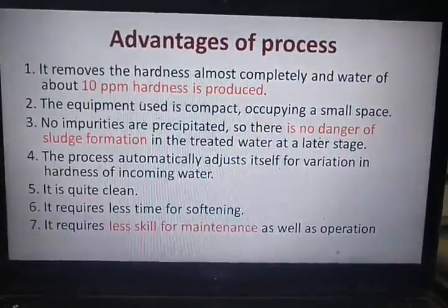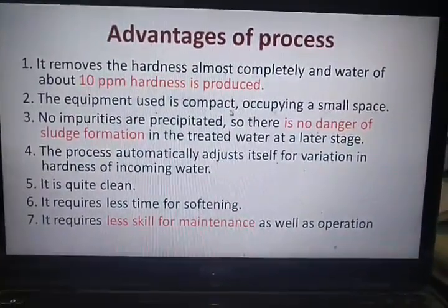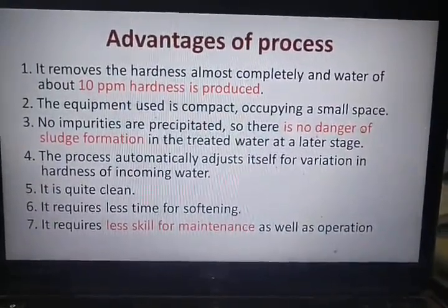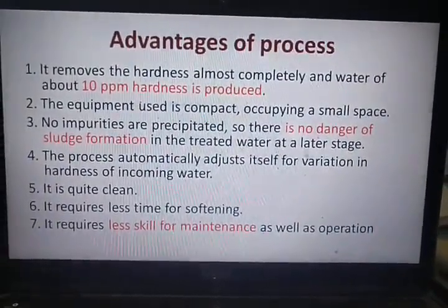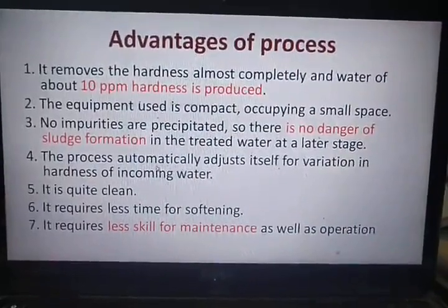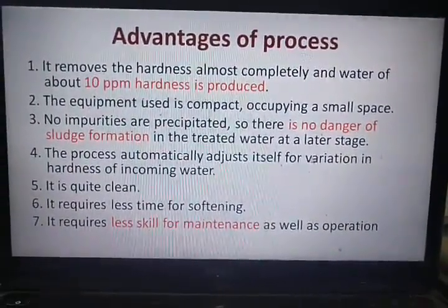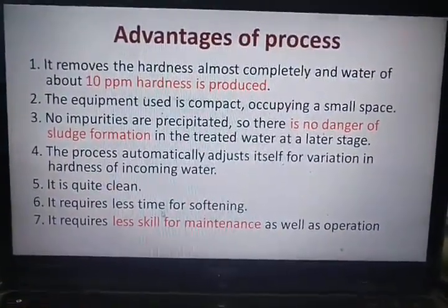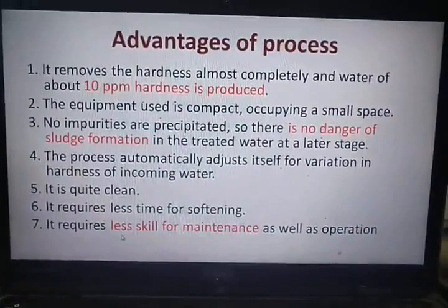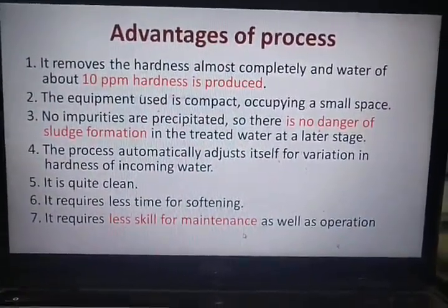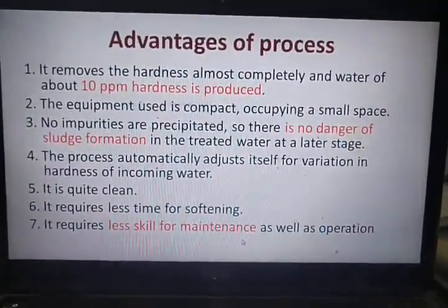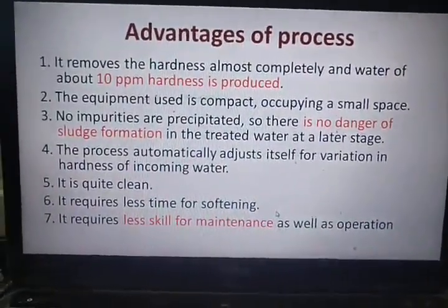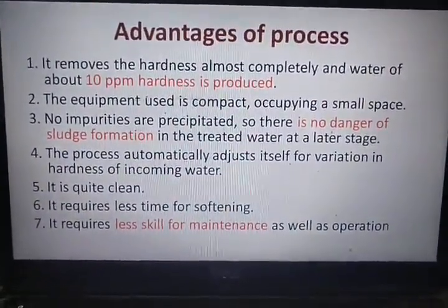The equipment used is compact and it occupies very small space. Here no impurities are precipitated, so there is no danger of sludge formation in treating water at a later stage. The process automatically adjusts itself for variation in hardness of incoming water, and this process is quite clean, and also it requires less time for softening. It requires less skill for maintenance as well as operation, and also here the zeolite can be regenerated, and that is also one of the advantages of this process.